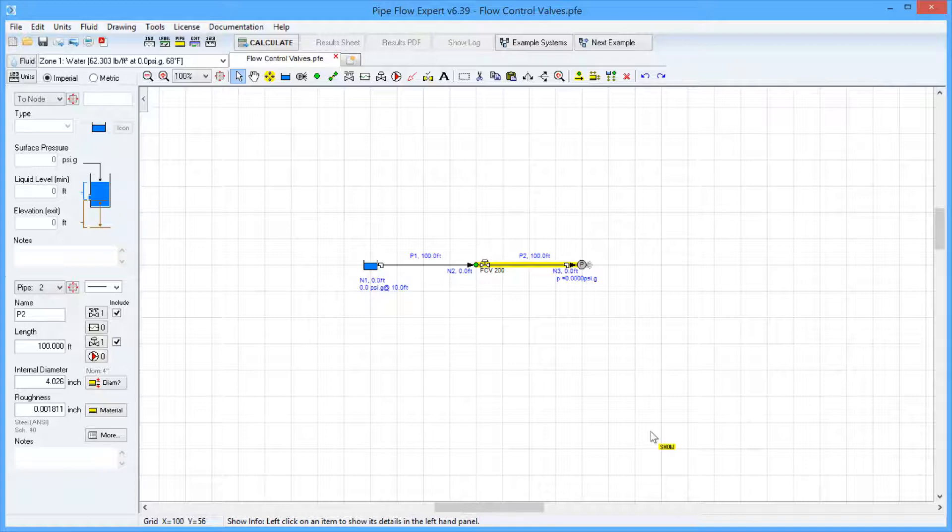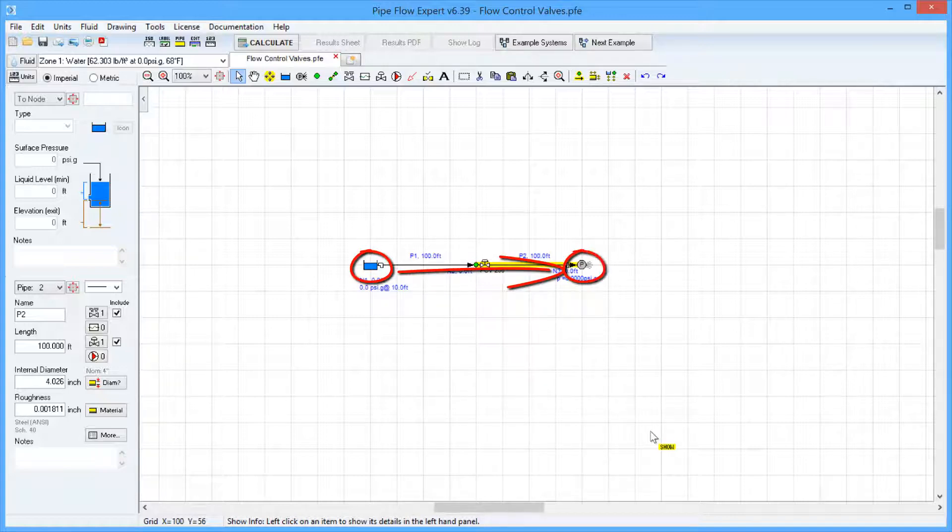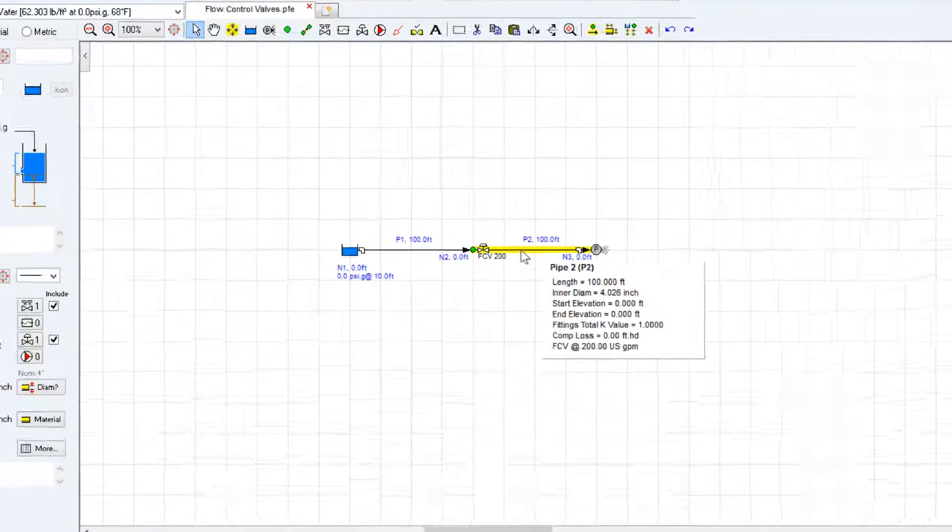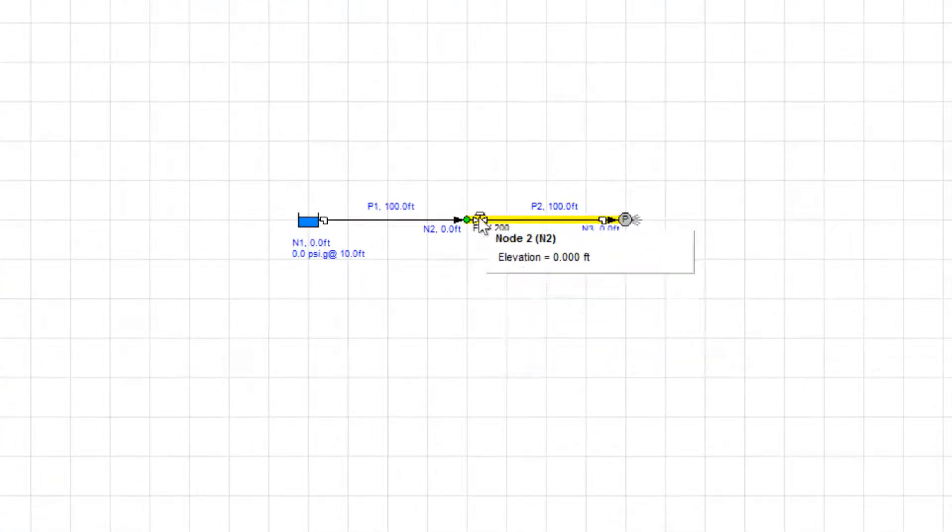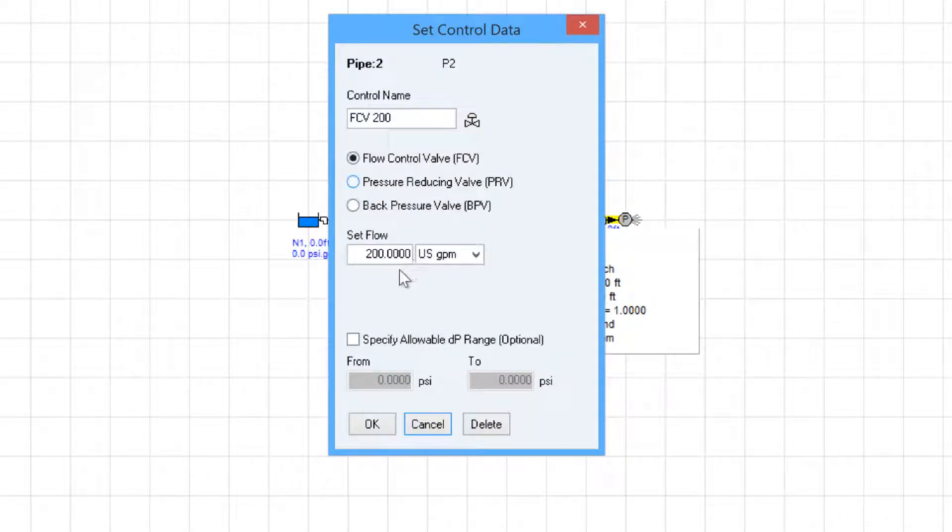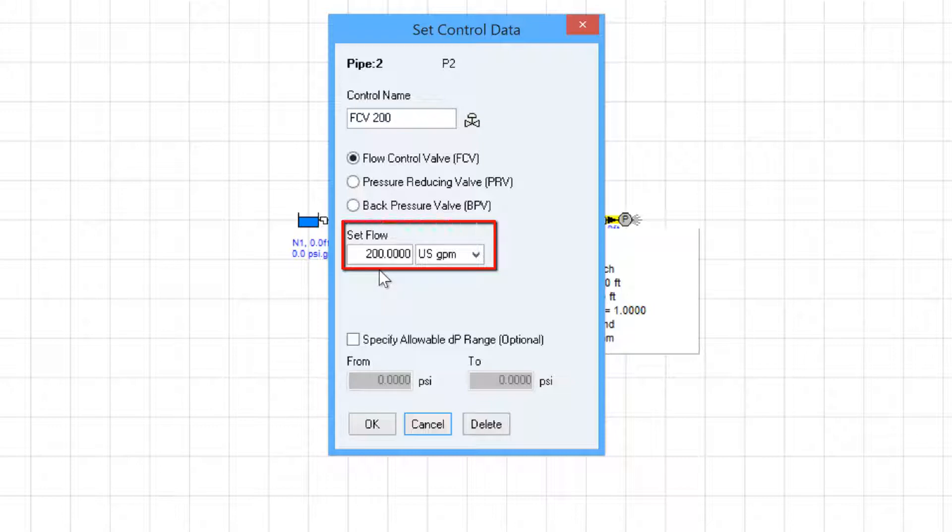In the system on the screen, we have a simple arrangement where there is a tank connected by two pipes to an outlet pressure. On Pipe 2, we have a flow control valve, and if we click on the icon for the flow control valve, we can see that it is set to control the flow at 200 US gallons per minute.